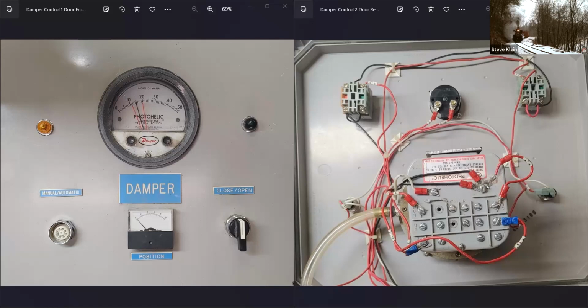Yours is actually operating a Venturi, same thing as a damper. You're narrowing it to increase the airflow past the water sprayer. It probably was just the poor actuator wearing out, because you'd move it and it would creep back against the force of the air.